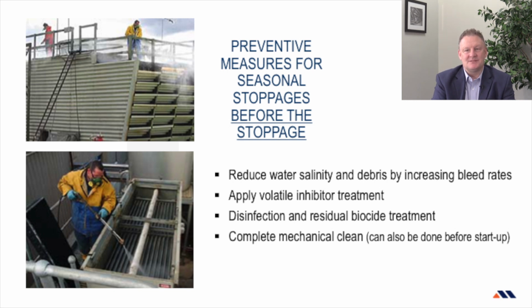Once the deconcentration has been carried out, one day before the stoppage, it is recommended to add a biodispersant as well as a non-oxidizing biocide to preventatively disinfect. Note that biocides such as bromine, chlorine, as well as glutaraldehyde are the ones that should be avoided during the storage period. 6 to 8 hours after adding the biocide and biodispersant, a volatile inhibitor treatment should be applied to create a lasting protection on all the surfaces. This treatment will effectively protect all surfaces, even the humid and submerged areas.